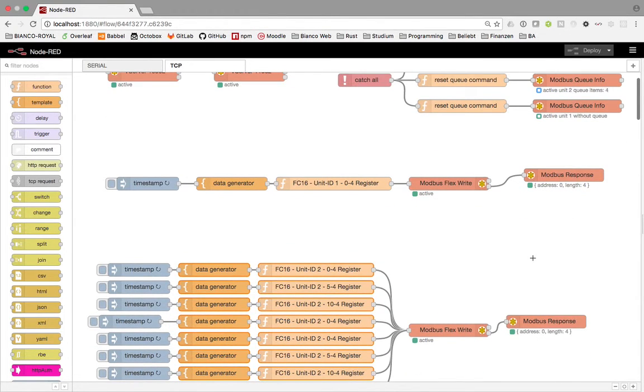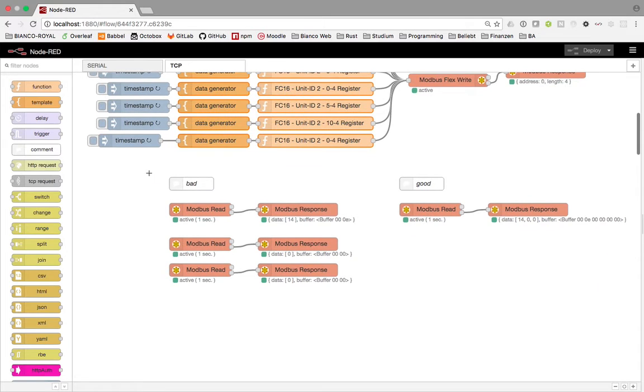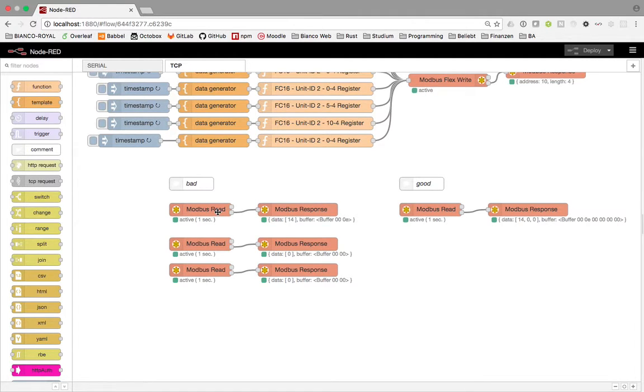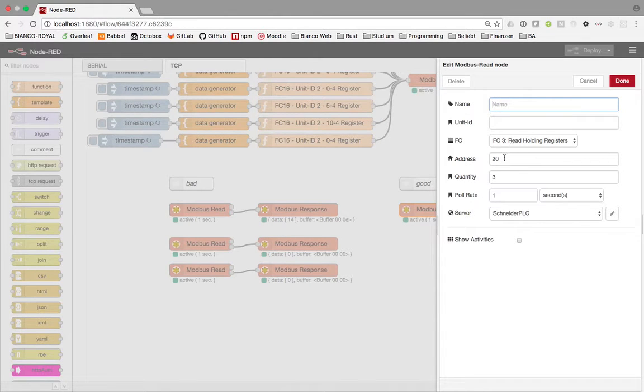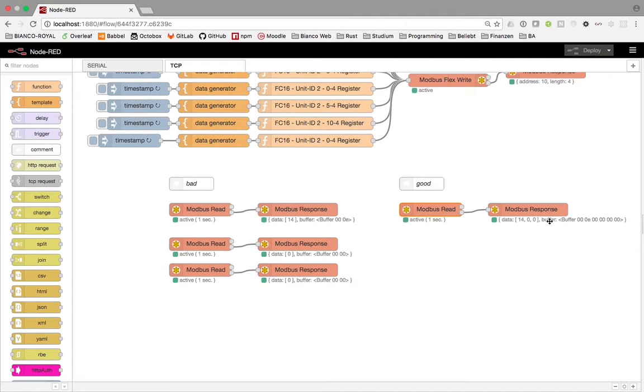That's the best way to decide whether to use a queue or not. Another best practice for reading and writing to Modbus is to use one node for close registers or coils instead of separate nodes for registers 20, 21, and 22. The better way is to have just one node and set a quantity of 3 — then you get all three values in the response and at the data output.